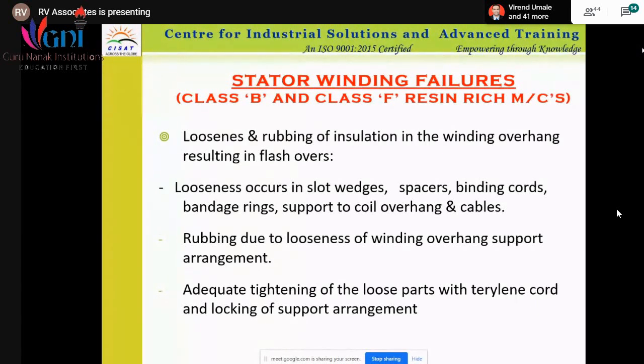That's called looseness. And whatever the distance is between two terminals, if that distance is not maintained properly, there will be arcing. It's like welding. That arcing will also lead to failure of the insulation. So this is the major one. It's not a small one that only the winding will fail, but this looseness happens at any place. It can be at the cable, at the joints, at the distribution boxes. So all looseness has to be tightened. That's why whatever thermography we have done will always give you information about loose connections at the terminal boxes.